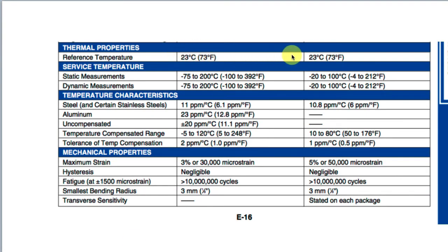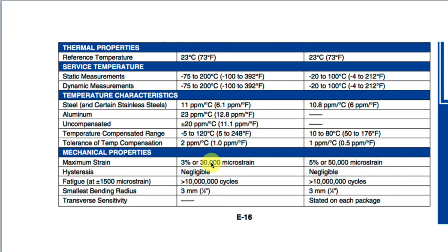You'll find specifications about the temperature range these devices work in. Temperature characteristics describe how much variation in measurement you'll see when mounted on different elements, and how large the variation is if uncompensated. With temperature compensation, you can get down to very small temperature-induced variations. Maximum strain is a key specification — these gauges can go up to 3% or even 5% strain, but for measurements on metals we're usually looking for much smaller strains.